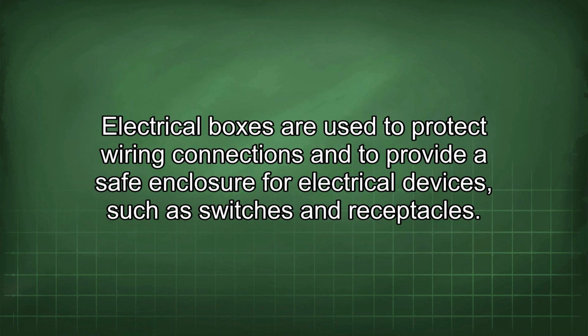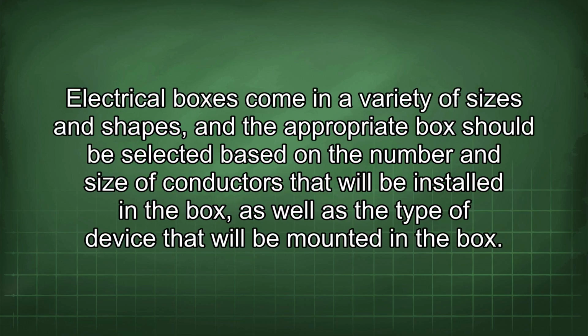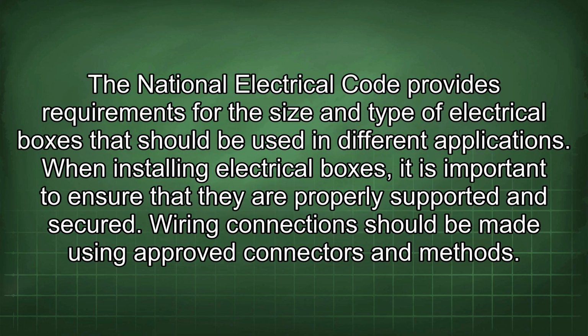Electrical boxes are used to protect wiring connections and to provide a safe enclosure for electrical devices, such as switches and receptacles. Electrical boxes come in a variety of sizes and shapes, and the appropriate box should be selected based on the number and size of conductors that will be installed in the box, as well as the type of device that will be mounted in the box. The National Electrical Code provides requirements for the size and type of electrical boxes that should be used in different applications. When installing electrical boxes, it is important to ensure that they are properly supported and secured. Wiring connections should be made using approved connectors and methods.